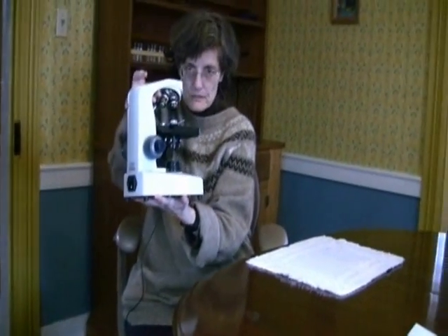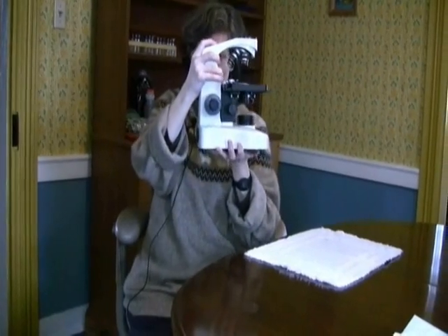Time to put our microscope together. It's arrived either in some kind of carrying case or in the box from the manufacturer, and now we have to put the pieces together. First thing you want to do is take the back of the microscope out, and that's going to be this big piece.